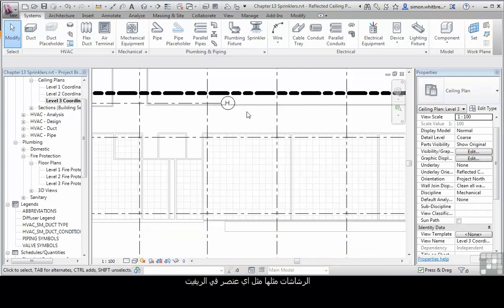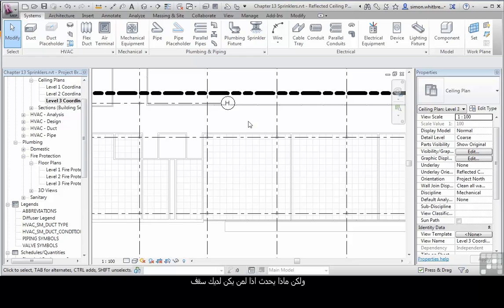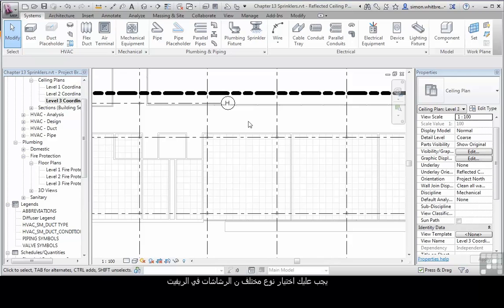The sprinkler objects, like many other objects in Revit MEP, can be hosted or non-hosted. Placing them on something like a ceiling or a side wall hosted sprinkler head is a relatively easy process. But what happens if you don't have a ceiling? What if they're exposed sprinkler heads with exposed pipework? Then you have to choose a different type of sprinkler head.